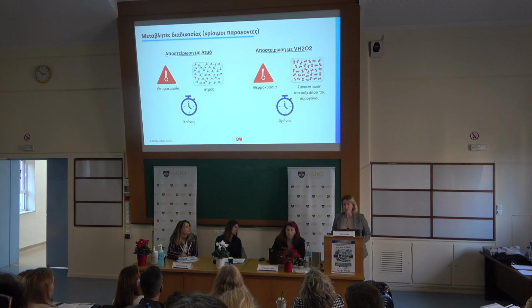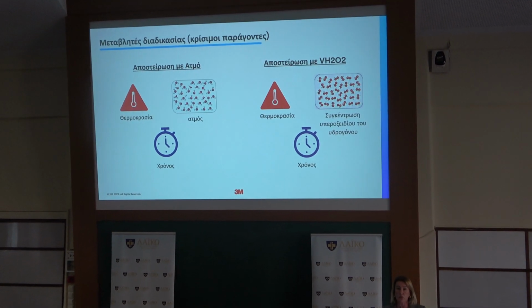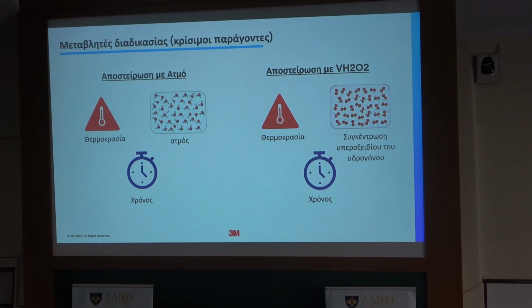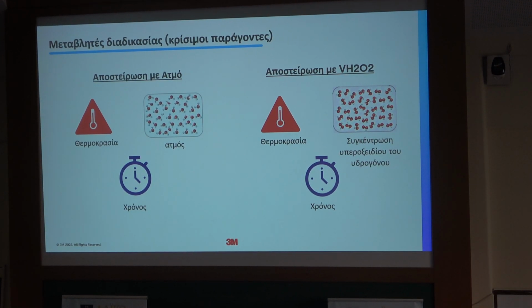While monitoring sterilization, it's also important to know about the critical variables, both for steam and for low temperature sterilization. For steam, we have time, temperature, and saturated steam, the quality of the steam, which is the main factor, because while monitoring we always try to see the quality of the steam. For low temperature cycles, such as vaporized hydrogen peroxide, time and temperature are there, but it is also important to have the agent concentration. If it is vaporized hydrogen peroxide, it is the concentration of hydrogen peroxide.